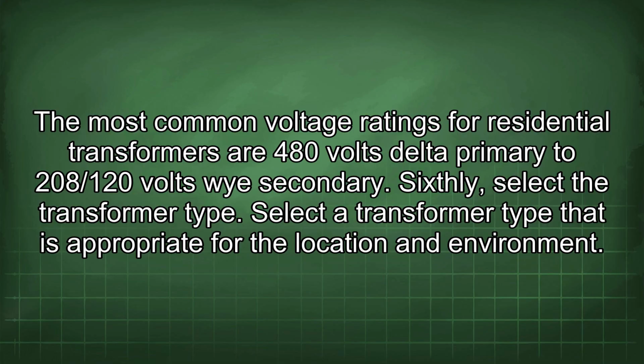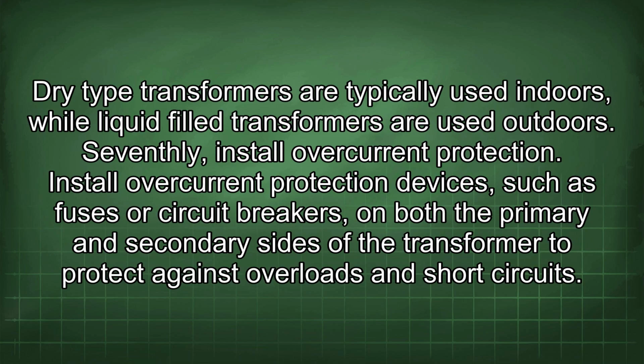Sixthly, select the transformer type. Select a transformer type that is appropriate for the location and environment. Dry-type transformers are typically used indoors, while liquid-filled transformers are used outdoors. Seventhly, install overcurrent protection. Install overcurrent protection devices, such as fuses or circuit breakers, on both the primary and secondary sides of the transformer to protect against overloads and short circuits.